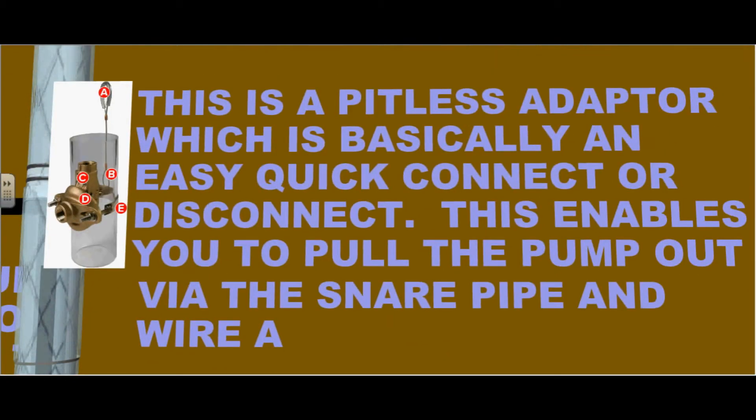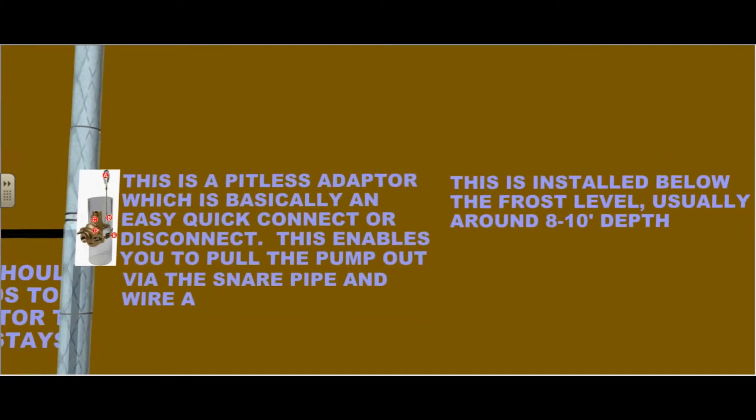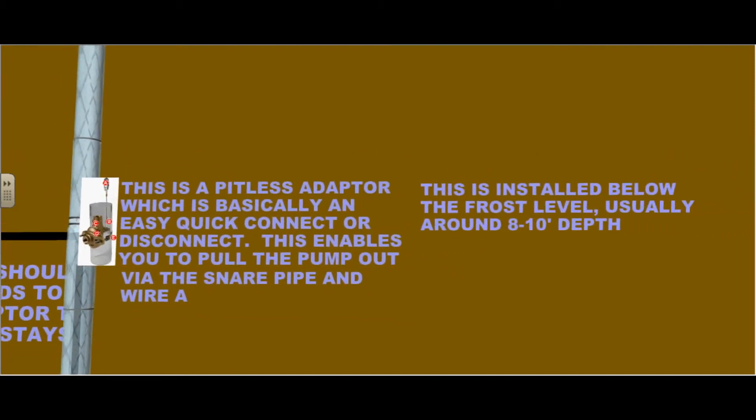This is a pitless adapter which is basically an easy quick connect or disconnect. This enables you to pull the pump out via the snare pipe and wire. This is installed below the frost level, usually around 8 to 10 foot in depth.